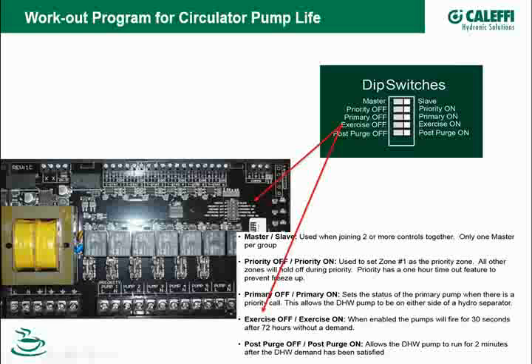Another good thing to do on your systems is have what I call a little workout program. There are relays on the market that have exercise programs built right into the board. This is one of our new Z1 relay boards, one of our pump relay controls. I don't know if you can see it in this picture, but there's a little switch in there that you can toggle that gives you an exercise program. Basically, if the pump hasn't run for 72 hours, it'll start that pump and run it for 30 seconds. We've got 6 different pumps in here, so whatever pump hasn't run for 72 hours, it'll fire that up and run it for 30 seconds.